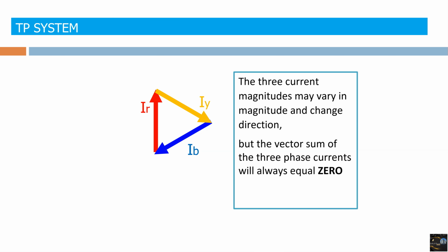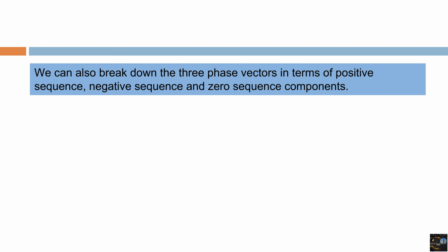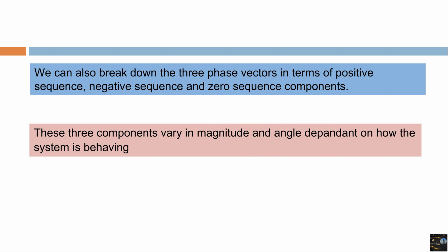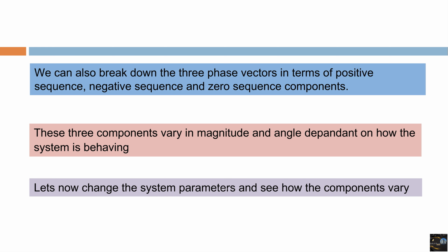The three-phase currents may vary in magnitude and change in direction, but the summation of all the vectors will always be zero, even in a TP system, same as we studied in the TPN system. We can also break down the three-phase vectors in terms of positive sequence, negative sequence, and zero sequence components. These three components vary in magnitude and angle, depending on how the system is behaving. Let's now change the system parameters and see how the components vary.